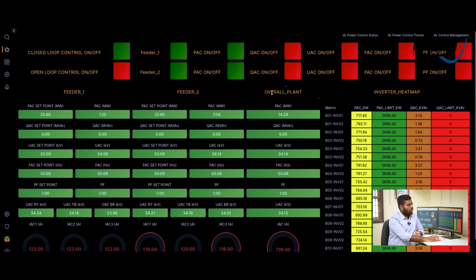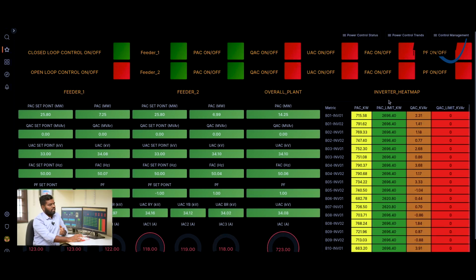Here this is the overall plant. Overall plant means overall plant active power, reactive power, voltage, frequency, power factor, here we can check. And this is the inverter heat map. The inverter heat map shows each and every individual inverter's active power and its limits, reactive power and its limits. In the inverter heat map, for example, greater than 75% of inverter capacity shows green color. 50 to 75% is blue color. 25 to 50% is grey color. 0 to 25% is yellow color. If not communicating, it shows red color.